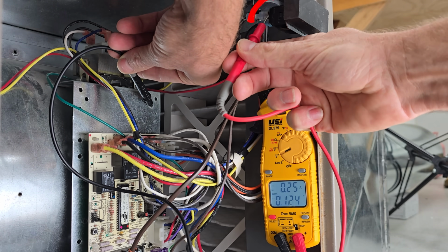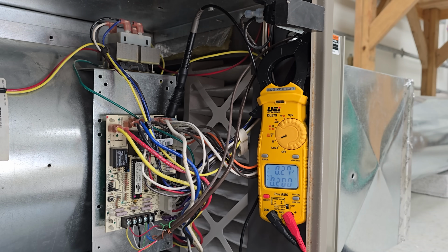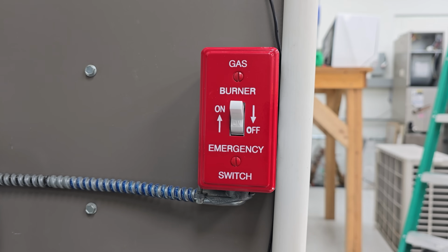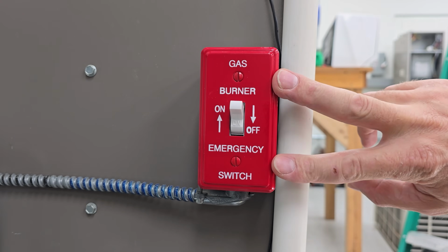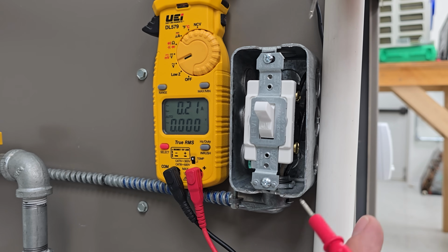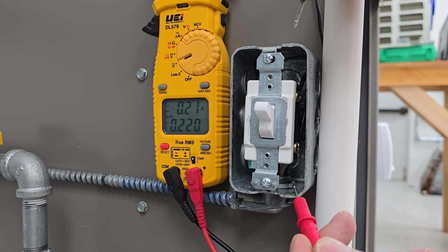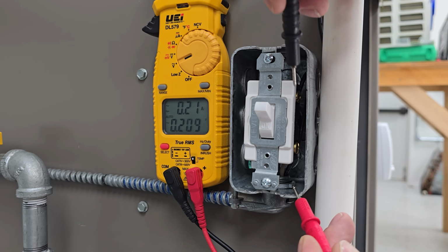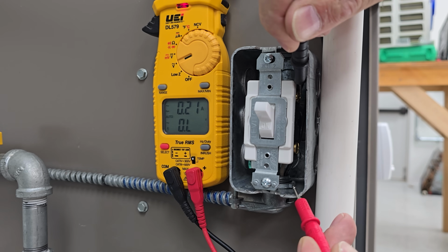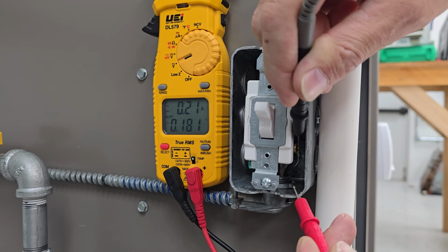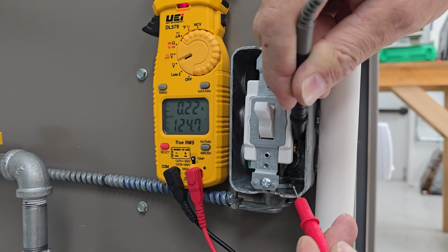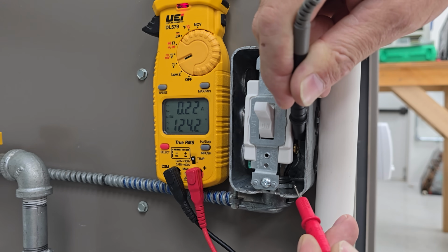So now we need to backtrack and go back up to the main electrical switch for the furnace. At this location, we're going to have to remove the 2 screws and measure for power. Now we're going to place one of these probes on the ground, because we can either put the probe on the ground or the common in order to measure for voltage. For the other probe, we're going to be very careful not to touch both the ground and the hot, but we're going to come back here close to the switch, and we're measuring 124 volts there. We're going to come down right along the plastic right there and measure at the other terminal, and we have 124 volts here, so we are losing our power between here and the door switch.